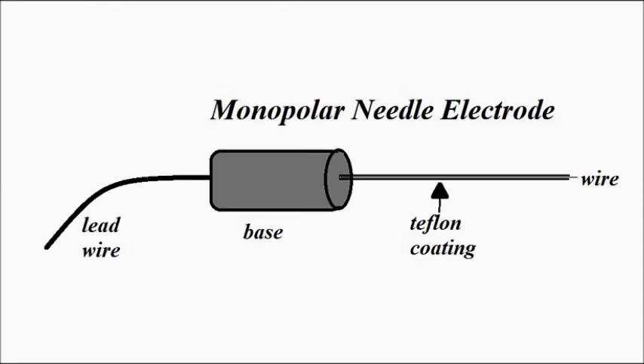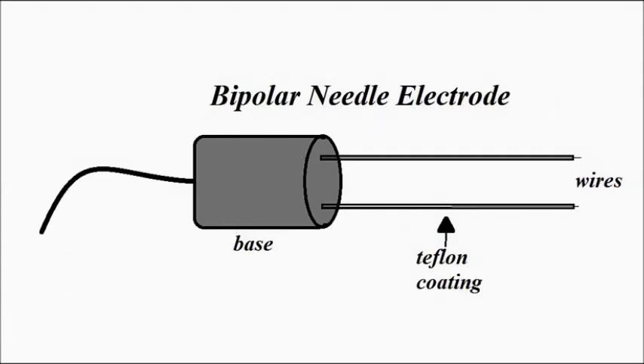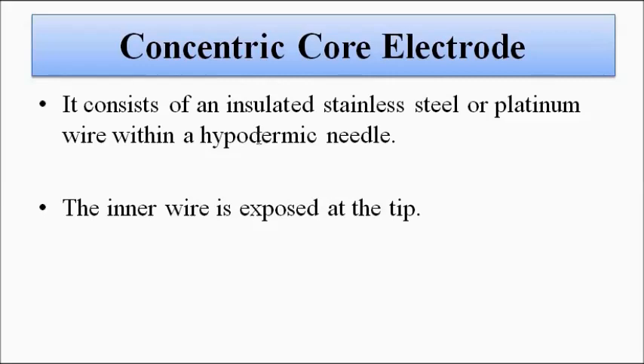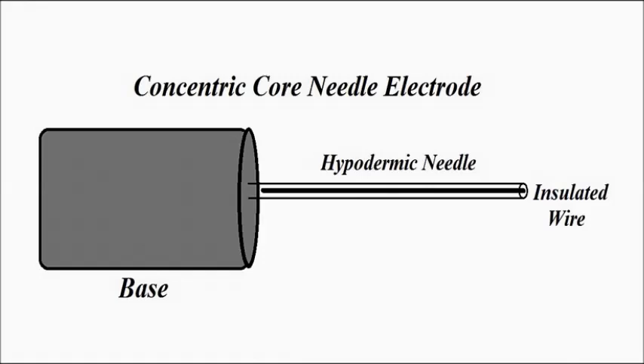Next is the concentric core electrode. It basically consists of a stainless steel or platinum wire placed within a hypodermic needle. It has a needle, and inside that needle there is an insulated stainless steel or platinum wire. Again, the wire is exposed at the tip because it has to be inserted and must facilitate signal flow.